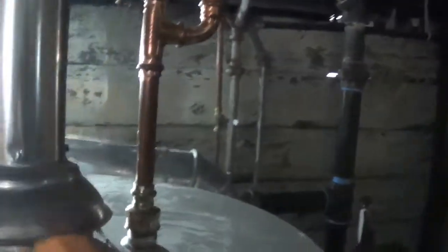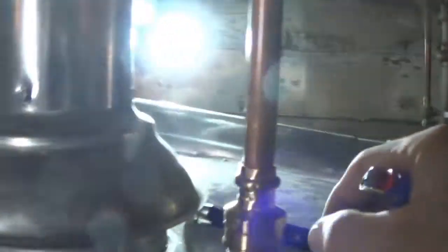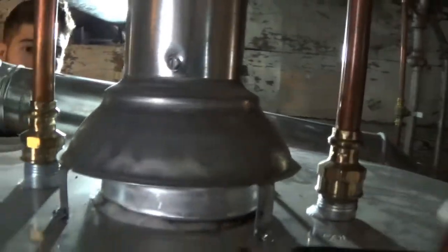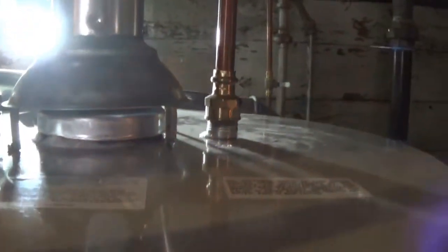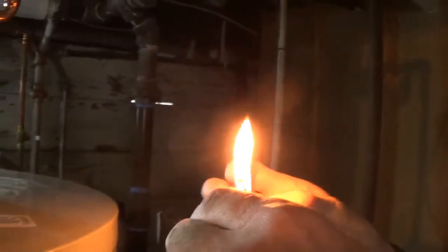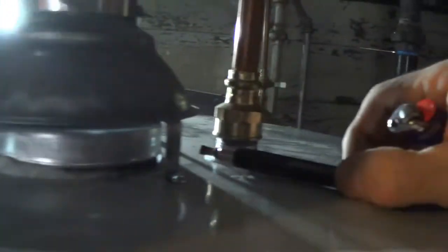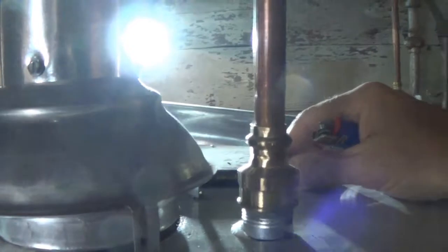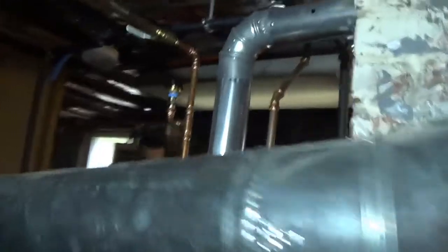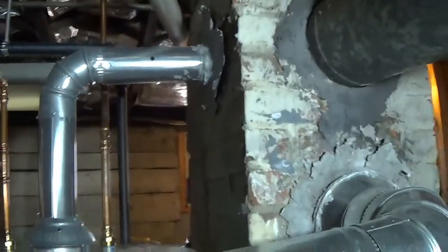Look at that. Remember it was failing miserably on this corner, and now it's doing great. That smoke is getting sucked sideways right up into that draft hood the way we like to see it. So under natural conditions, all by itself, after the flue has had a chance to cool down, we're getting better results here, here, all the way back around here. And it's not even 60 seconds yet. So this only gets better, honestly. You're not going to start to have failed spillage later. It's only going to get better. So that passes that. So we circle yes, passes spillage under natural conditions for our water heater.